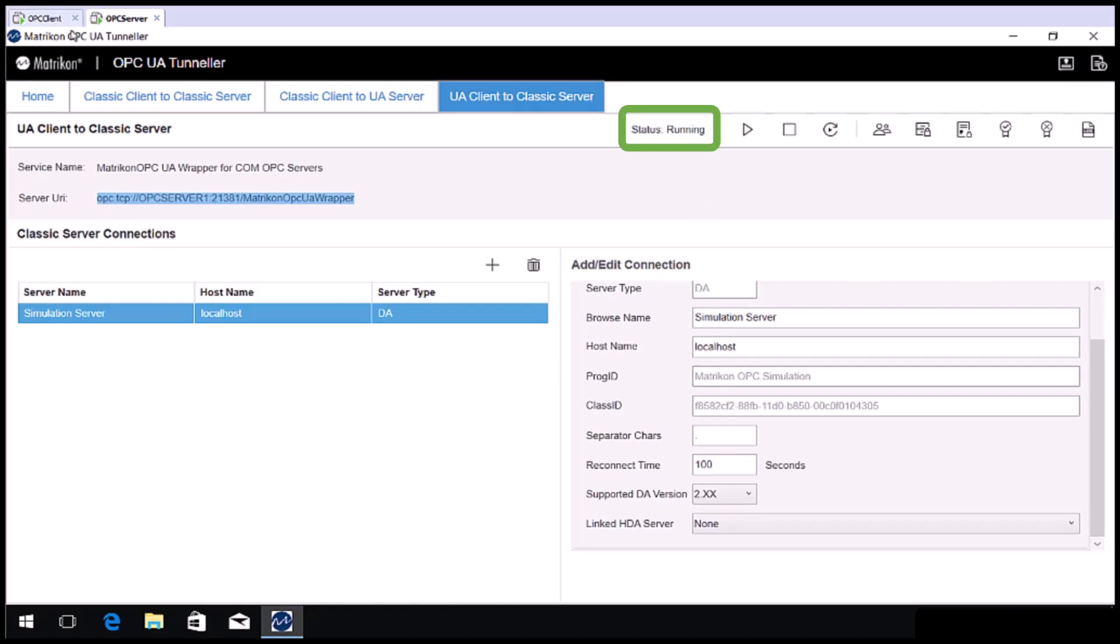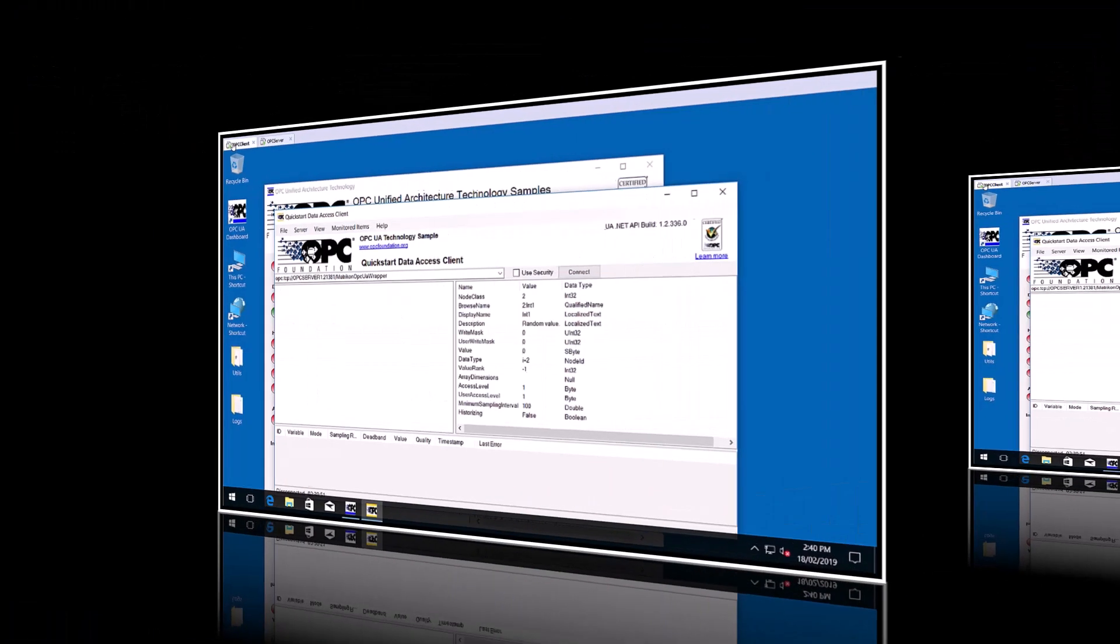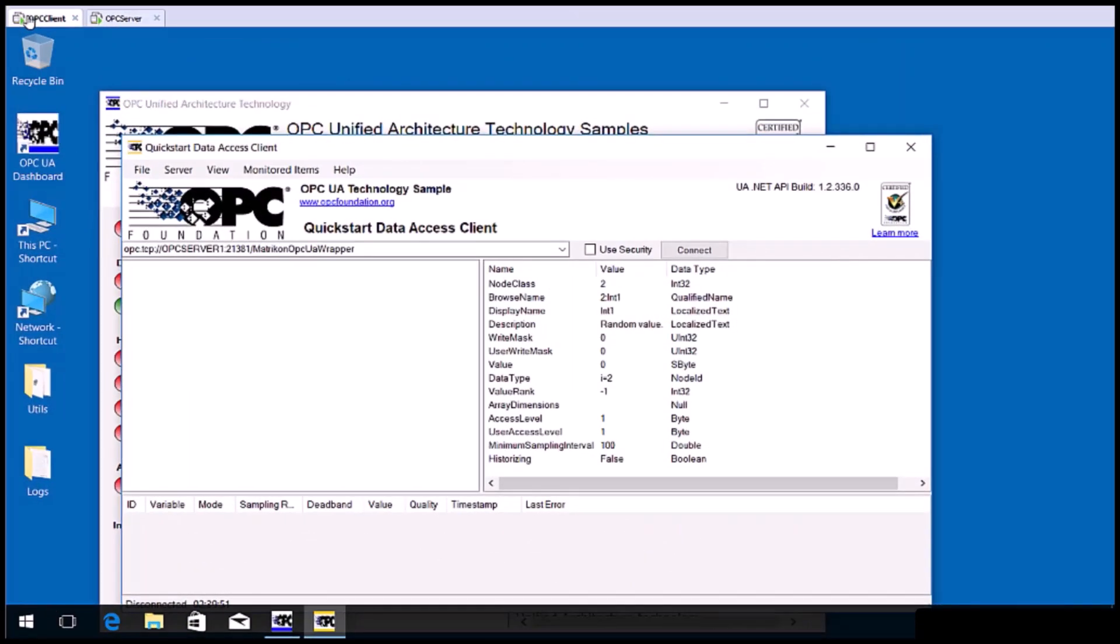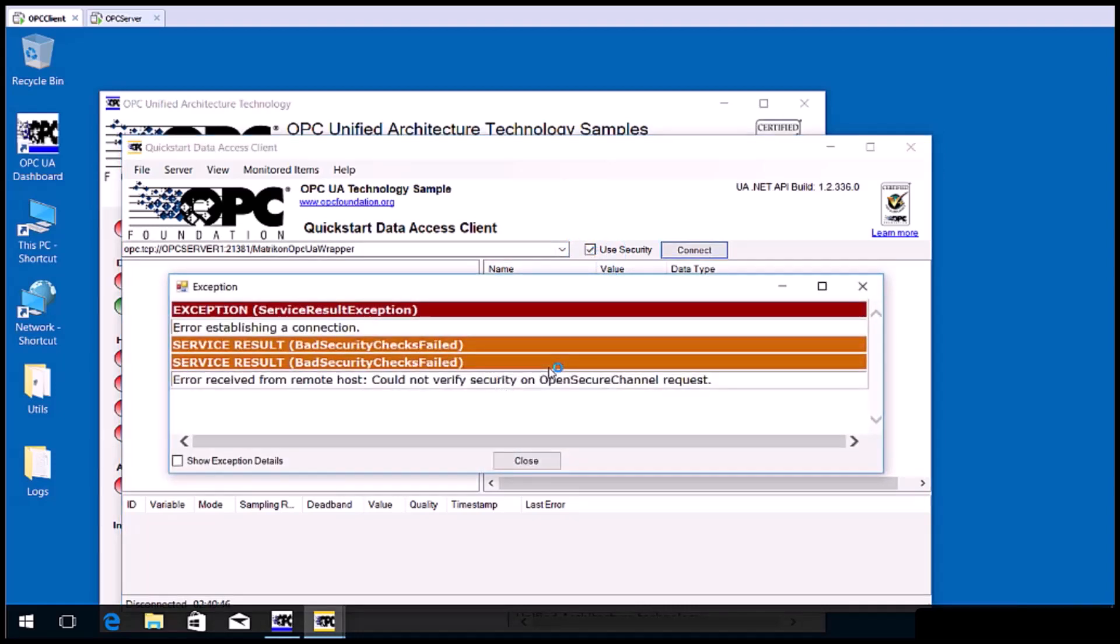Now go back to the OPC client computer. Confirm the URI is the same as before, but this time click use security. Then click connect. Note that the error that is displayed says error establishing a connection, error received from remote host could not verify security on open secure channel request. This indicates that the OPC UA server has rejected the connection request as it does not yet see this OPC UA client as a trusted friend. Click close.